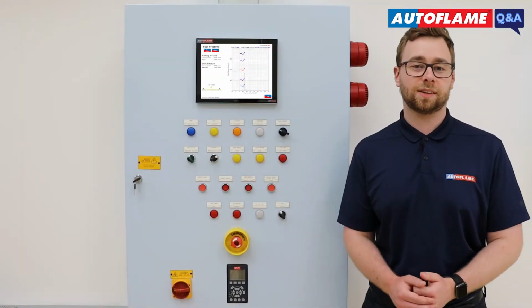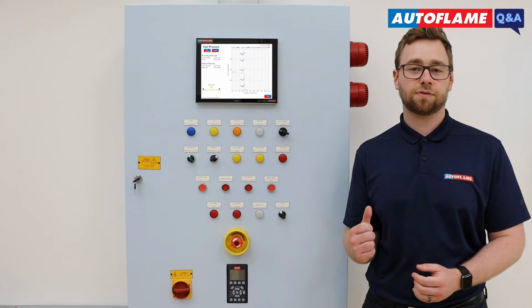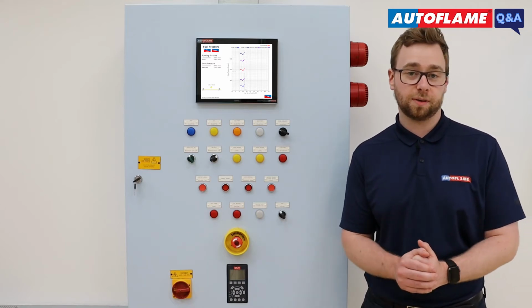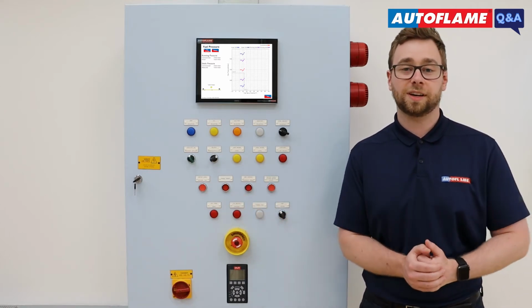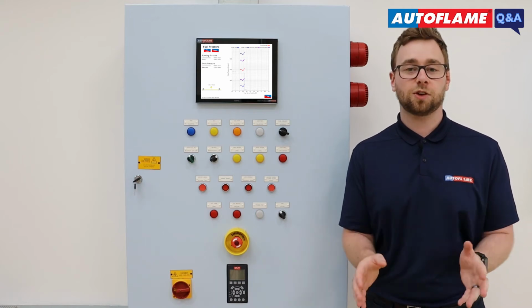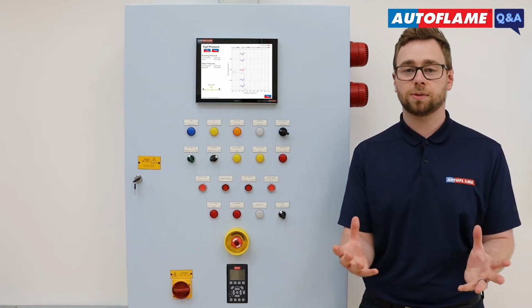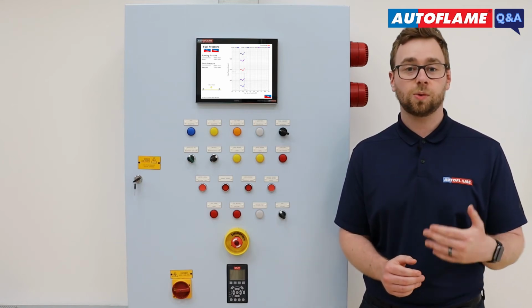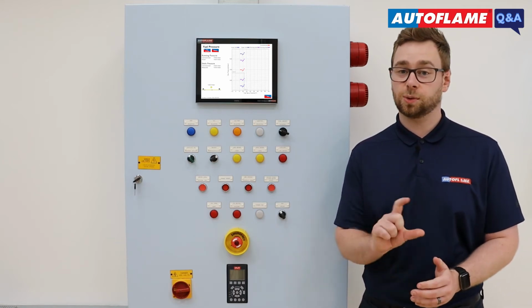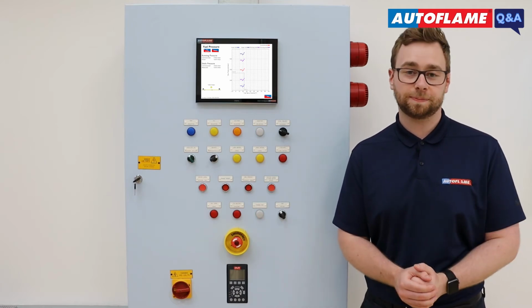When the gas pressure sensor or air pressure sensor is configured for monitoring and proving, the controller will run through your commissioned fuel air ratio curve, starting at low fire and stepping up to high fire, logging your pressure at each of your points. Now, configurable warning and shutdown thresholds can be set around your commissioned pressure curve. The warning threshold will generate a warning to the end user and store this in your system log, whereas the shutdown threshold will shut down the burner.